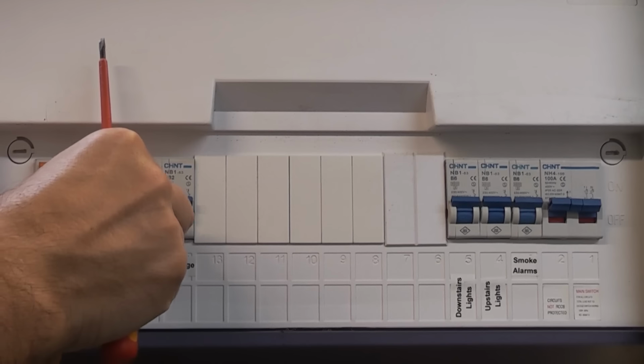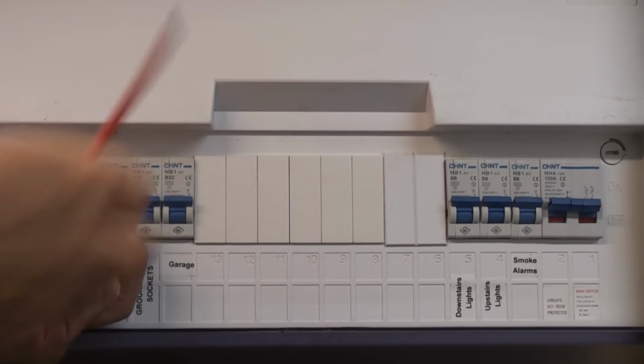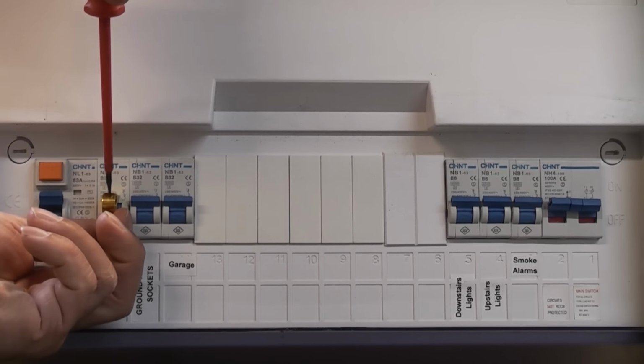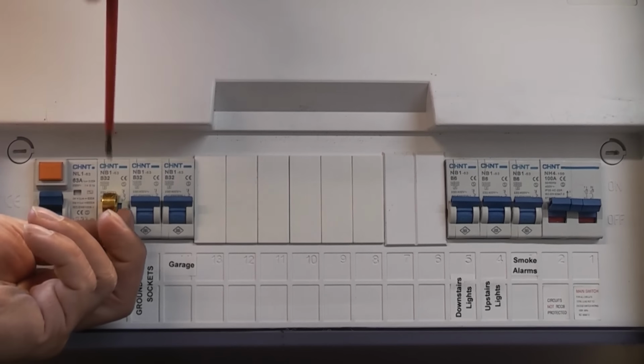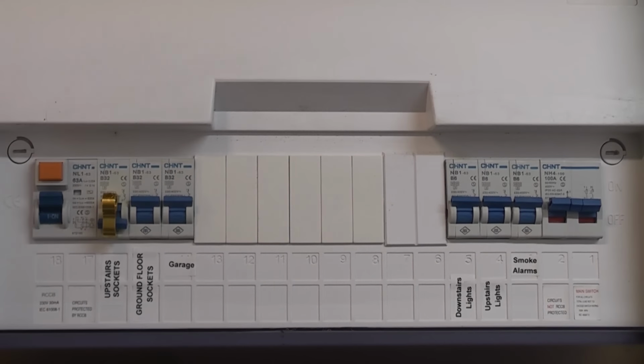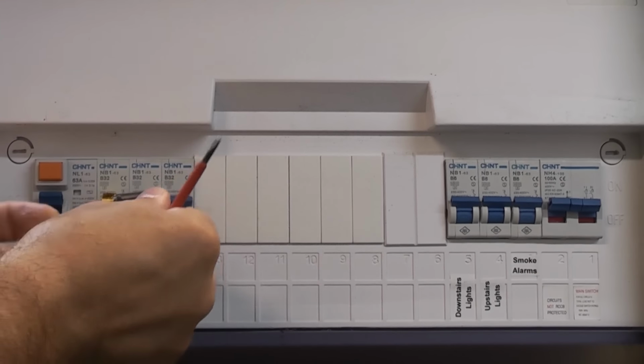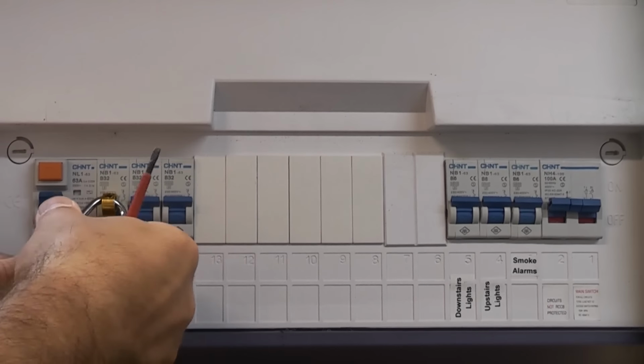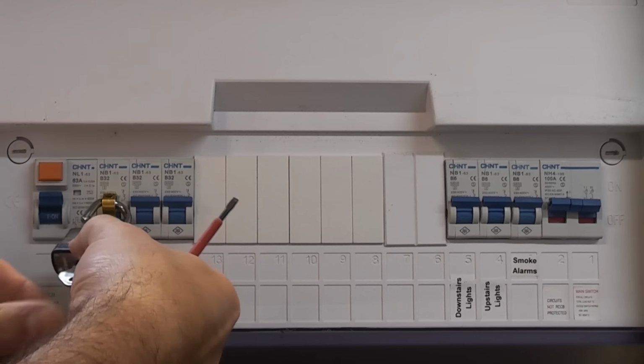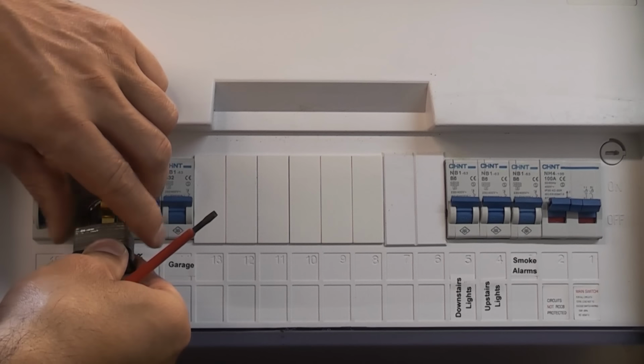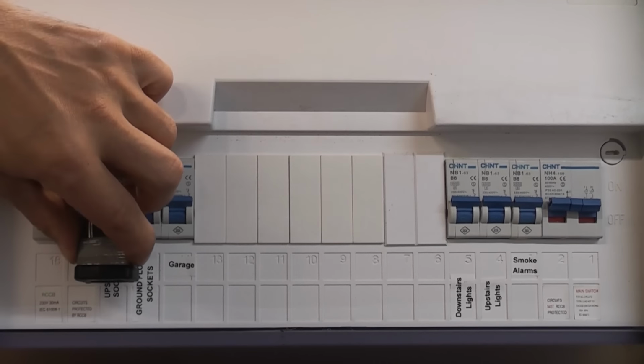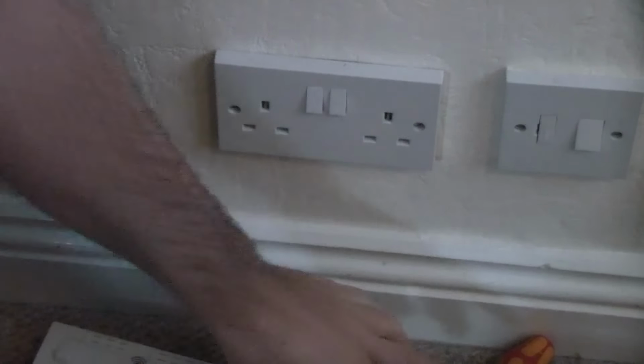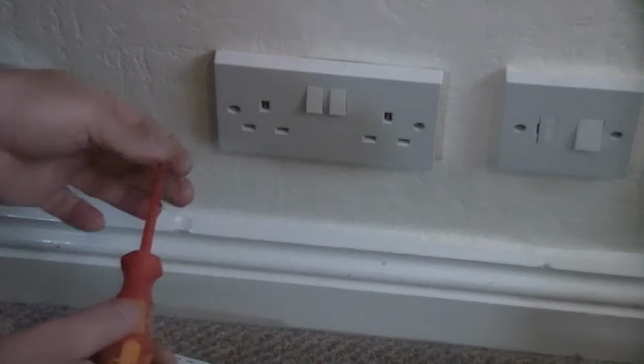I'm then going to use a lock-off device, and then a padlock and key to lock off that MCB. Obviously when you do this, you need to keep the key on your person at all times. Now that's gone off, we can remove that and proceed to remove the screws.